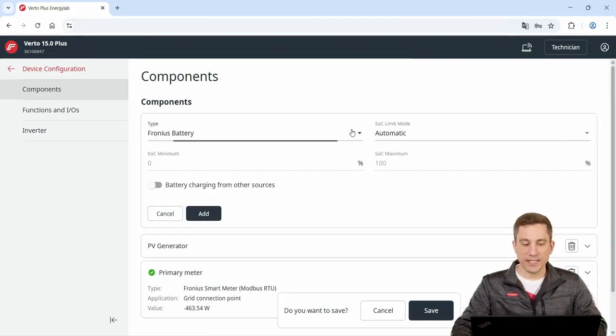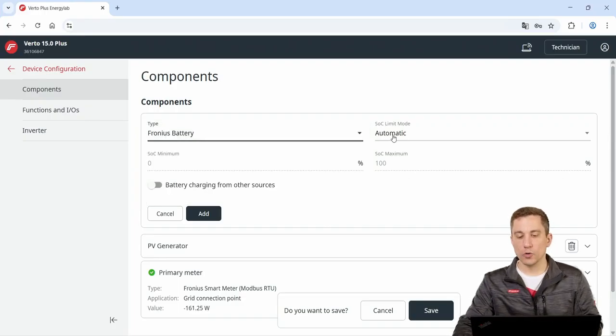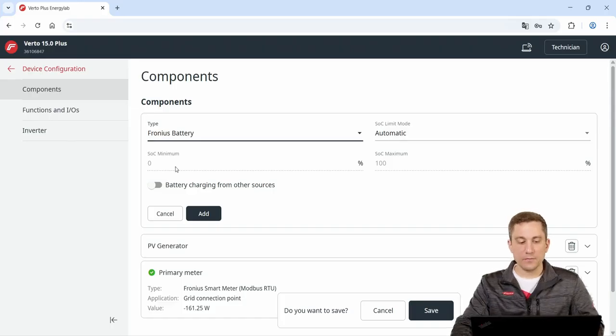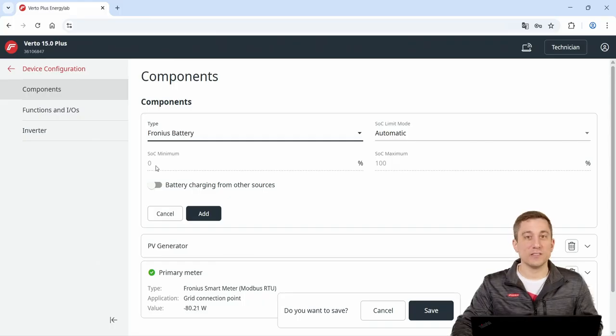And here, under the type, you can choose our Fronius battery type. And after that, we recommend you to set the SOC limit mode to stay on Automatic. There, the battery system will regulate itself from 0% state of charge to 100% SOC. And this is also our recommendation. So for the end customer, this is the most logical way that he can use his battery system from 0 to 100. No worries, of course, at 0% SOC, the battery is not really at 0%. We have a buffer beneath that to save the battery life.